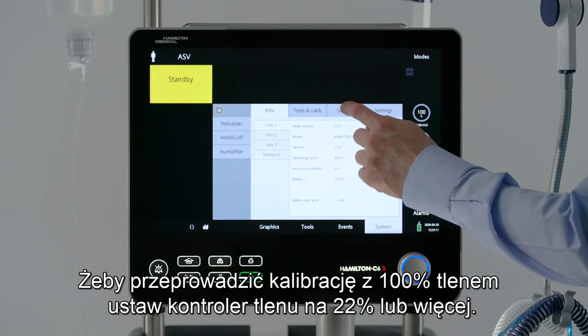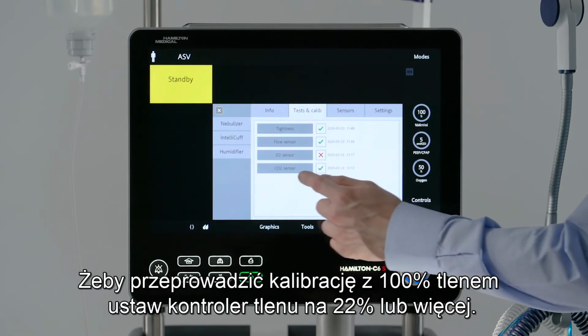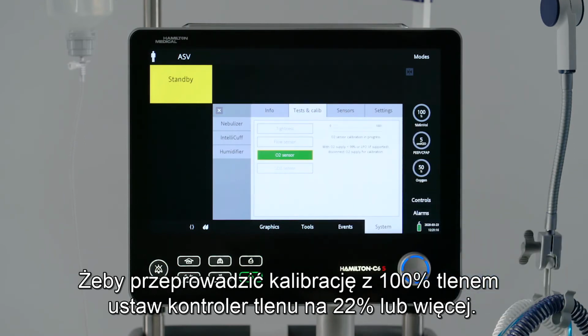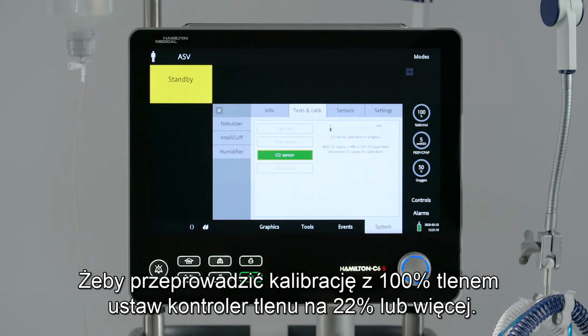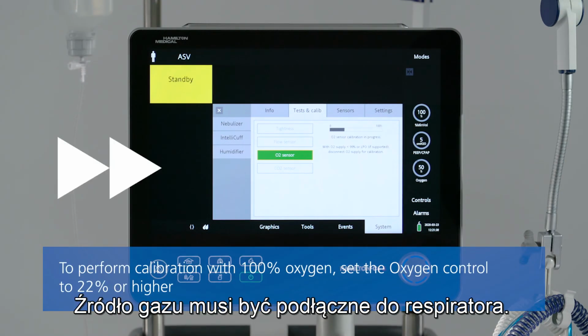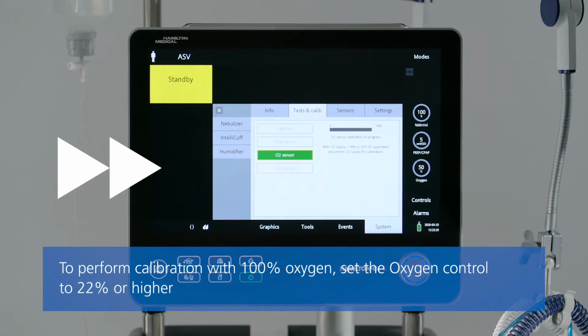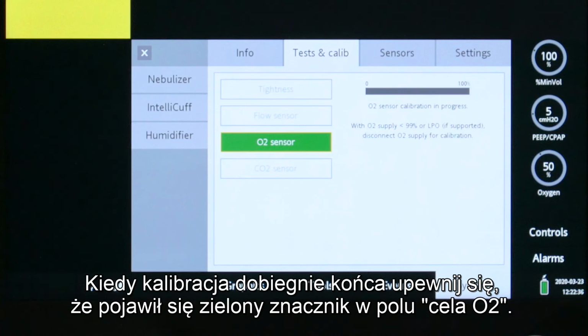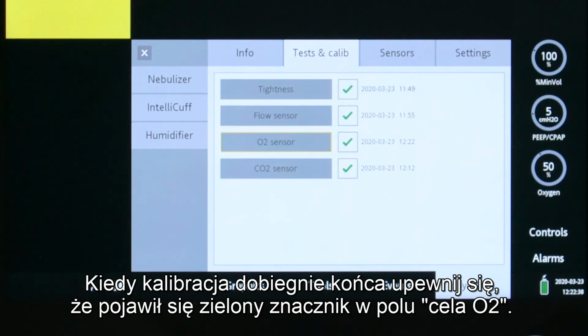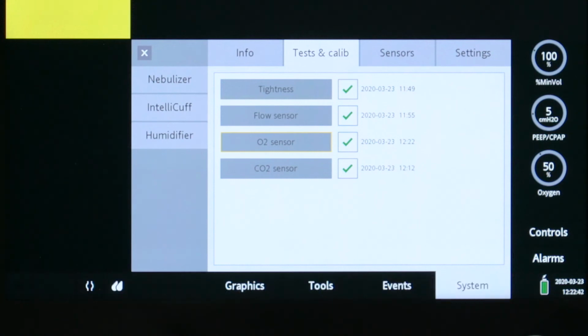To perform calibration with 100% oxygen, set the oxygen control to 22% or higher. The gas source has to be connected. When calibration is complete, make sure there is a green check mark in the O2 sensor checkbox.